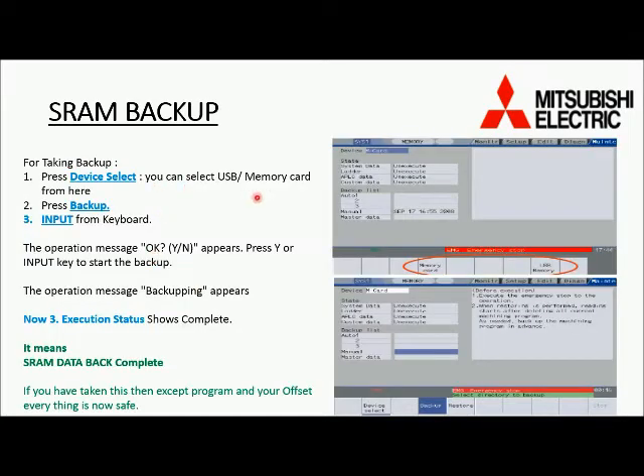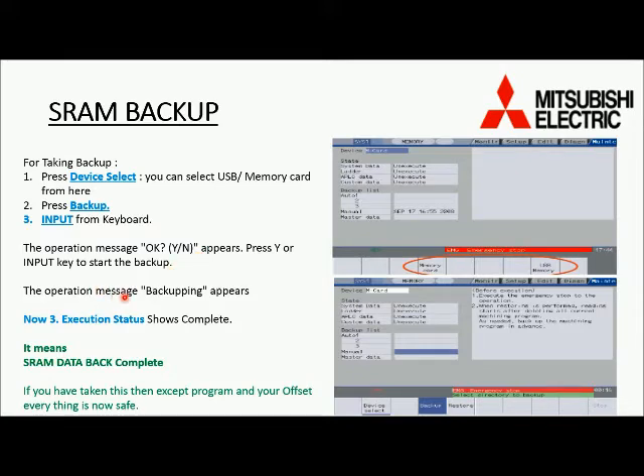To take the backup: first, press device select — you can select USB or memory card from here. Second, press backup. Third, after selecting the desired device, confirm input from the keyboard. Then the operation message OK appears with Y or N. Press Y and the input key to start the backup. The operation message backup complete appears when execution status shows complete.